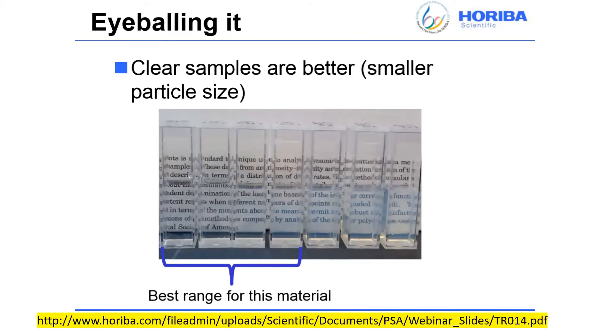The concentration affects the count rate — the strength of the scattered signal. There's a recommended range of count rates, so check your instrument's manual. Although the concepts are the same between vendors, the recommended values may differ.